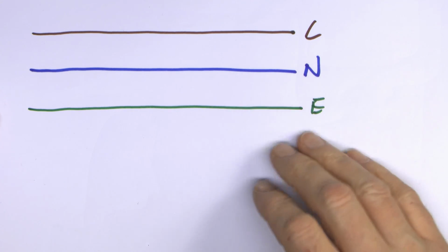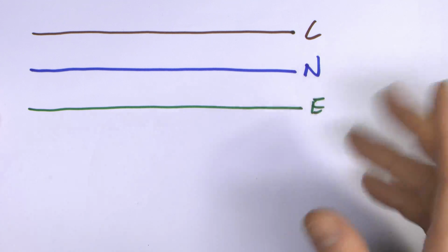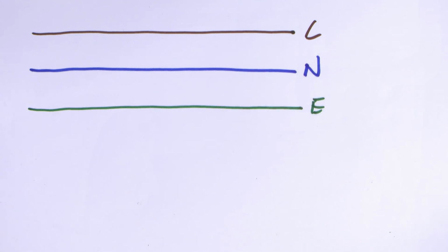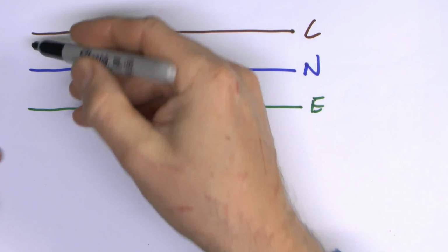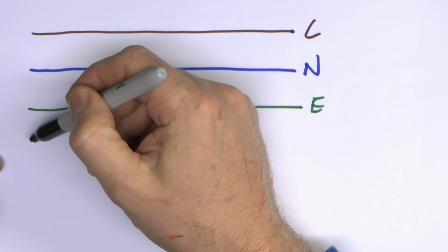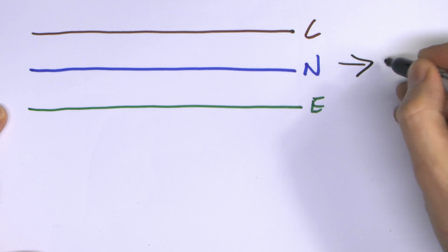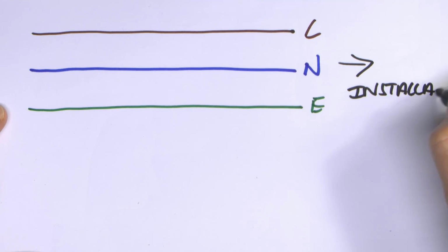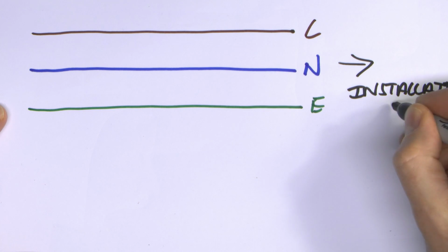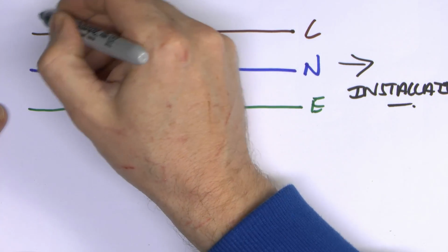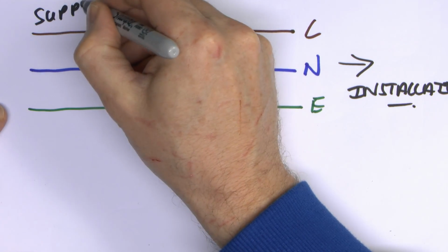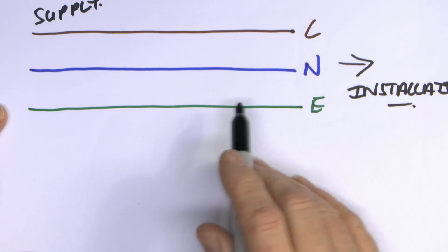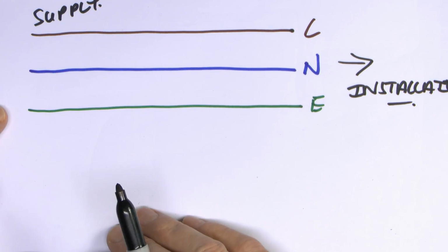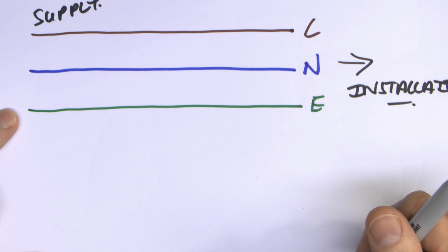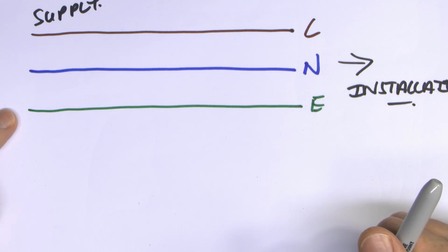And in terms of connecting it, there are several ways you can do this. What we're going to show first is basically the wrong way to connect it. So you can imagine that over here would be, say, the supply coming in, that might be your supplier's fuse or whatever, and then this will go to the installation, so the consumer unit or whatever else over there, and then we'll call this side the supply. So this could be like meter tails or whatever coming in from the meter over to the consumer unit or distribution board or whatever else you've got.